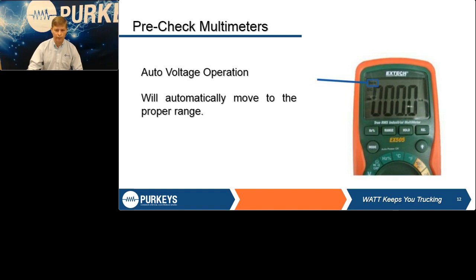The one thing you want to make sure of on this particular meter is up in the left-hand corner, it gives you a little auto. It says you're in automatic range. Some meters are opposite. Instead of saying auto, it'll say MAN or manual. That's if you think you're smarter than this meter, you can toggle through. Again, just like we talked about before, a 2-volt scale, 20-volt scale, 200-volt scale. And there are times that is handy. We've noticed that, depending upon the meter, when you get into a very low voltage, say less than 2 volts, the meter has a hard time locking in on those voltages. So if you manually put it on 2 volts, it will give you a quicker response and play the voltage back.